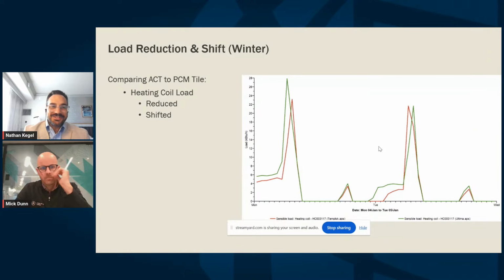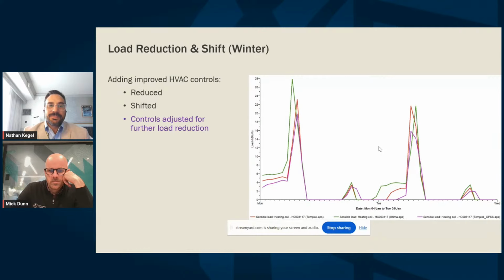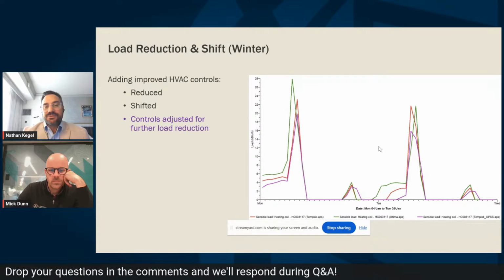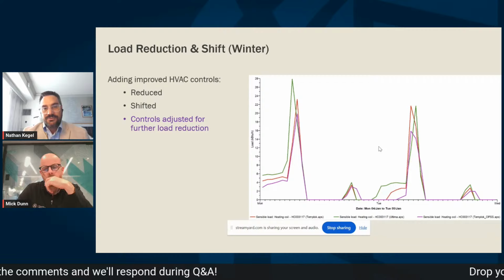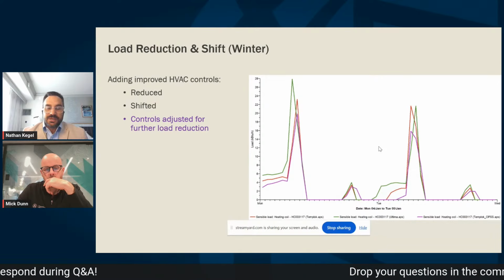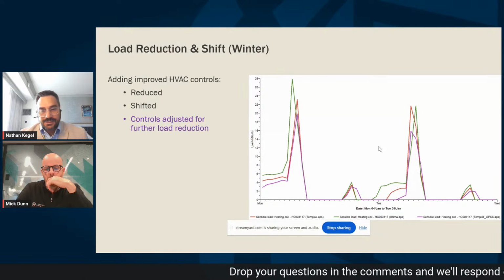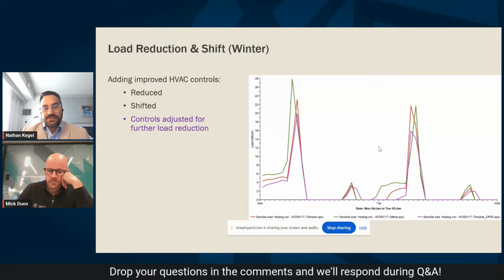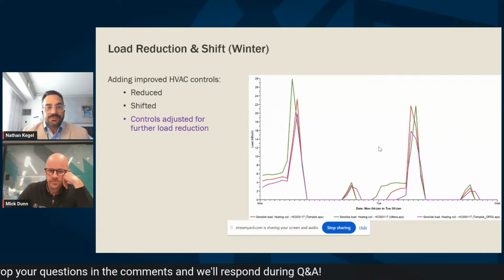Oh, I forgot I have a little bit more detail on this because I'm a nerd. So we have a bit more comparing the ACT, looking at the temperature or the load on the heating coil. The green line is the regular ceiling tile, and the red line is what happens to the load on the coil when phase change is applied. You can see a general reduction and shift. Moving to the next slide, this is where we adjust the controls to leverage that phase change or thermal mass even further. The purple line shows we've got a benefit, so let's take that benefit and extend it. You can see the reduction in peak load is even more pronounced and shifted slightly as well.